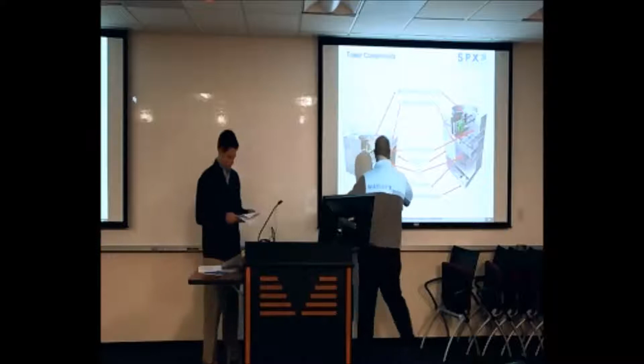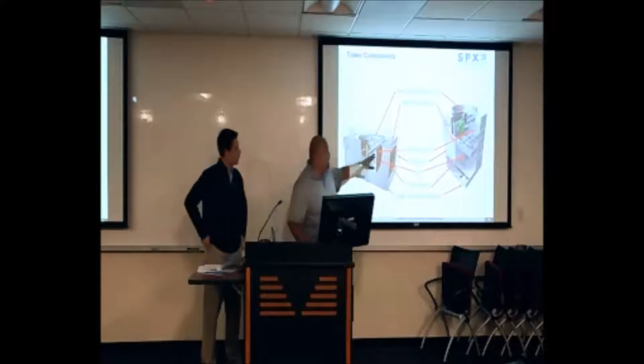Also on the hot water basin, because the water's warmer, coming in at your set point of 95 in the middle of summer. We've got covers here, which we ask that you keep covered. A lot of times we find that they're open, and there's a lot of leaves and debris that gets in there. Make sure that you keep it covered. Nothing bad happens immediately if you leave it open, but debris, animals, birds get in, and that's where a lot of the mold and algae starts to grow. So be very careful, because that's where all the water gets introduced to the tower, and that's where your fill's going to get affected.